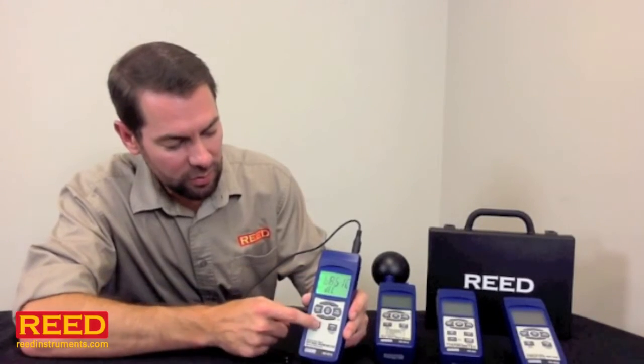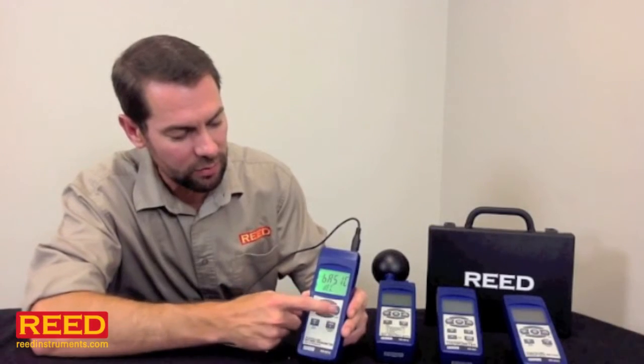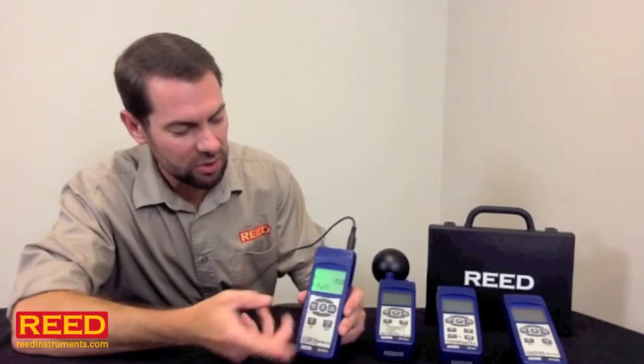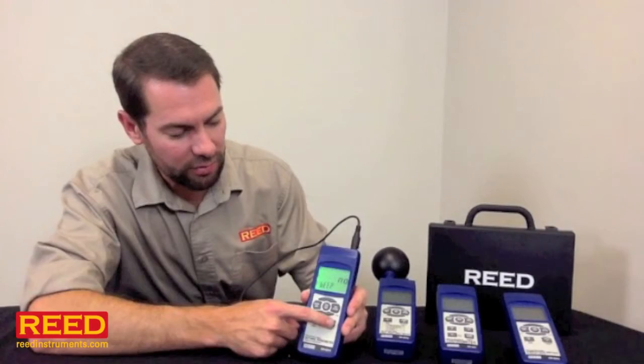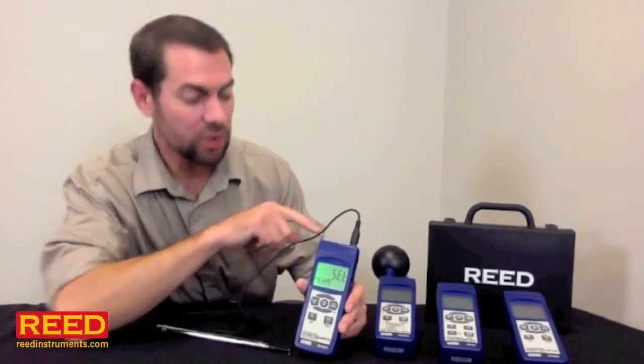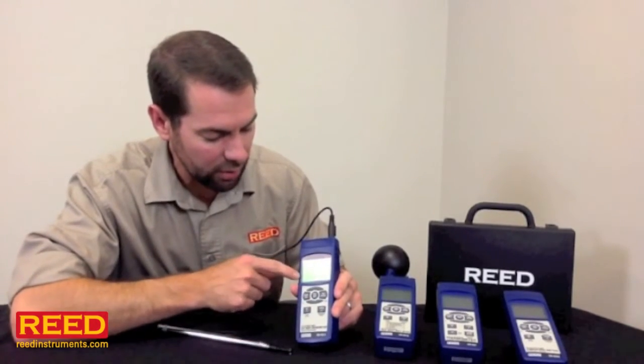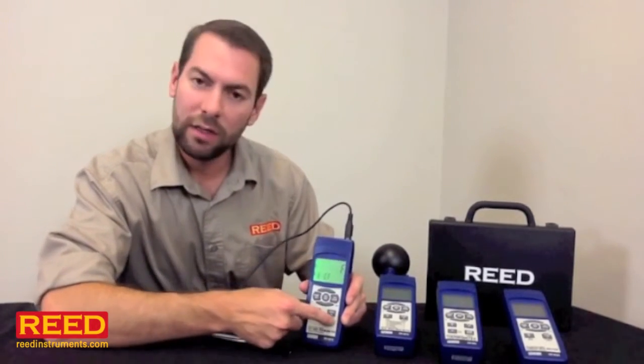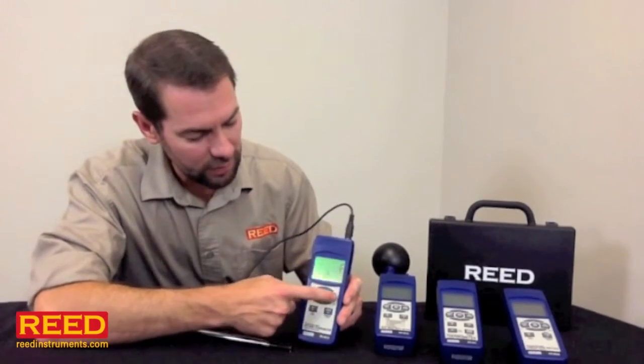Here it's going to ask you if you want to use decimals or commas. In Europe they use commas — let's keep it on decimals. Power off function: that just shuts it off over a certain period of time, let's turn that off. Hit enter again — do you want to turn that beep noise off or leave it on? It's kind of nice to know you're walking through the menu properly. Hit enter again. This unit takes a thermocouple probe, so it's asking do you want type K or type J. I have a type K probe, so I'm going to keep it on that. Hit the enter button one more time — it's going to ask if I want Fahrenheit or Celsius. Just leave it on Fahrenheit.